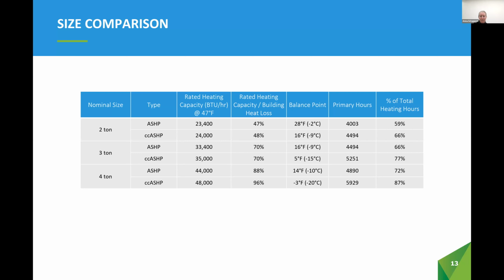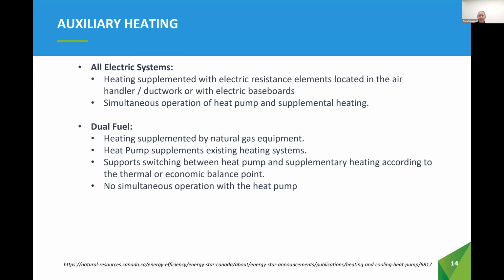Historically, air source heat pumps have only been paired with electric resistance auxiliary heating systems. Many of the systems on the market do not require or limit you to electric resistance backup. Air source heat pumps can be paired with fuel-fired equipment such as natural gas boilers or furnaces.